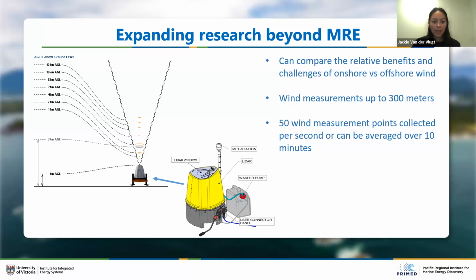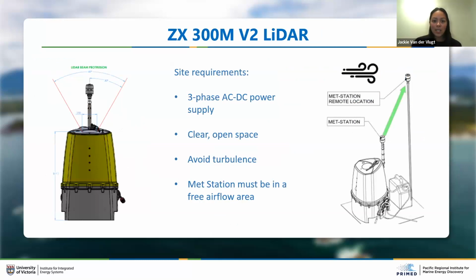So the image on the left just gives you a little visual on how it works. So there's that 60-degree cone that you see. And on the left side of that image, there's all the different heights that the LiDAR unit is taking measurements at. And so as the wind passes through there, those 50 points per second measurements are taken. Deploying this instrument offshore is a little bit easier than deploying it onshore, and that's because offshore there's no neighboring buildings obstructing the LiDAR beam or nearby objects that may cause turbulence.